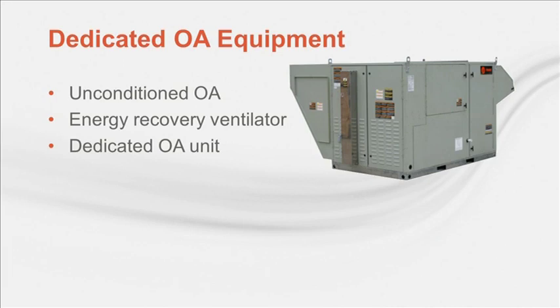In most applications, the use of a dedicated outdoor air unit is preferred, since it can adequately dehumidify the outdoor air and not rely on the VRF terminals to have to do so. Often these are standalone air-cooled DX units like the example shown here. These are simple to design in that they do not affect the sizing of the VRF system. And they can be operated for after-hours humidity control without the need to operate the VRF.